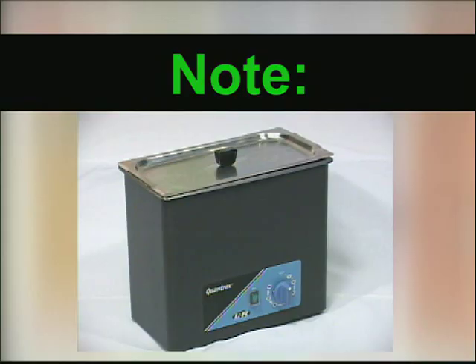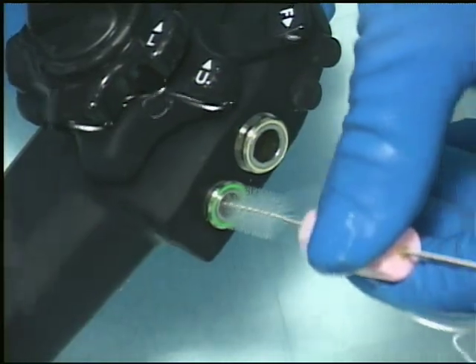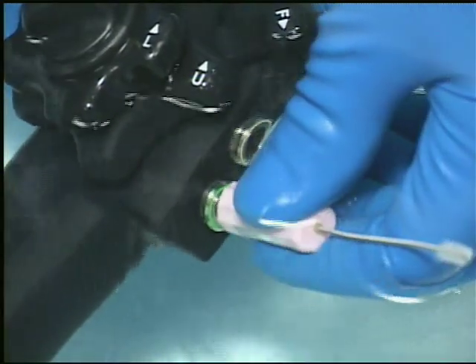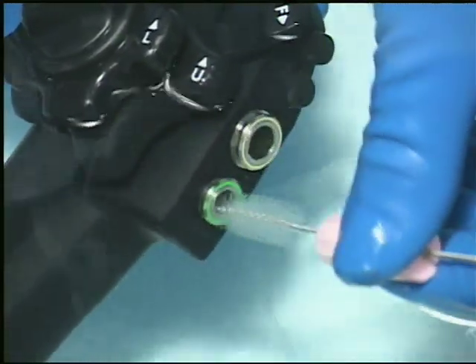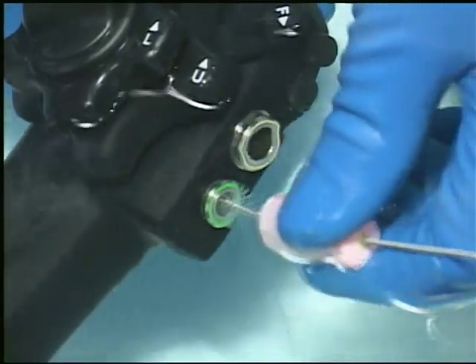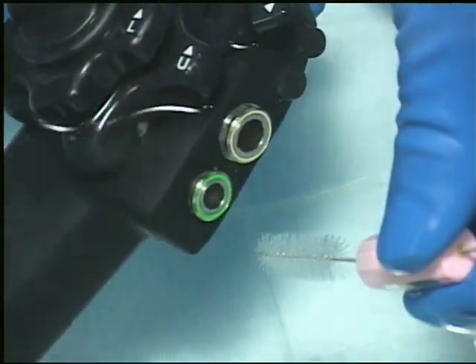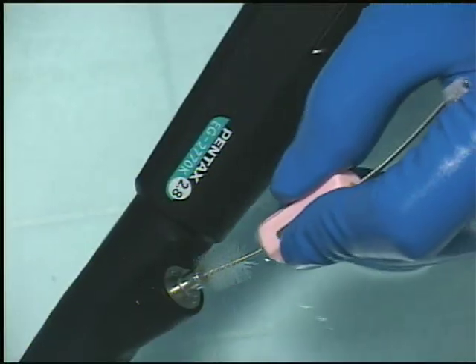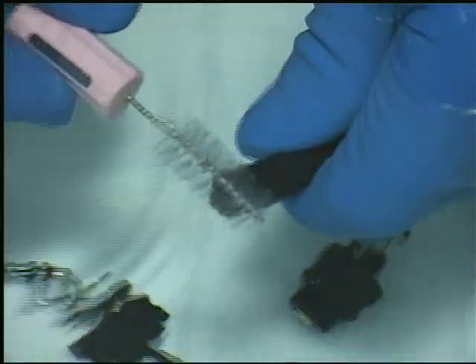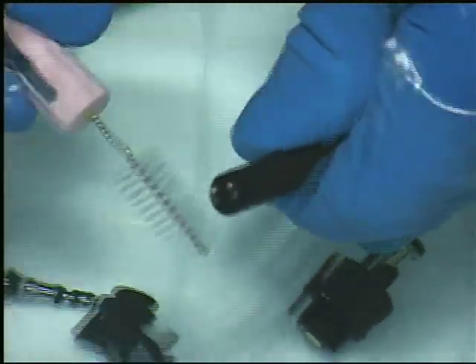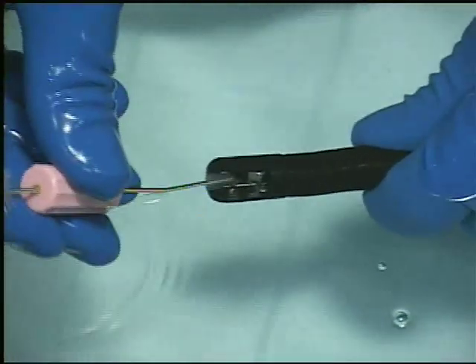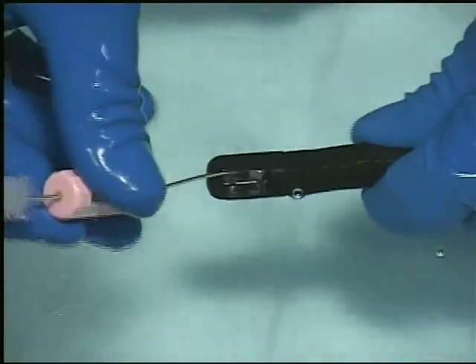This may be completed after manual cleaning by brush and soaking in detergent, but prior to subsequent high-level disinfection or sterilization. Using the larger end of the cleaning brush, scrub clean the surfaces inside the air-water cylinder. Make sure that all recessed areas of the endoscope, including valve cylinders, channel openings or ports, distal tip, air-water nozzles, elevator mechanisms, etc., are manually cleaned.